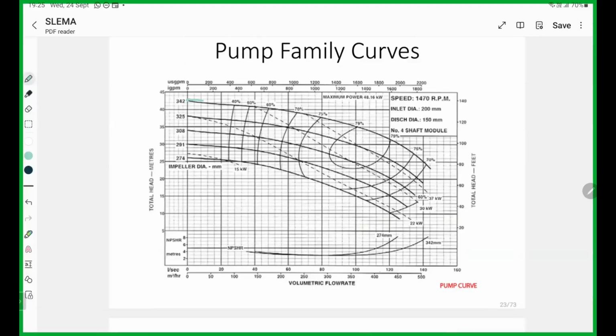This is higher impeller diameter. Then you can choose your impeller diameter and system curve. Then you can select your pump as per your requirement. You have to provide your head and flow basically to select the pump. Then accordingly, the pump manufacturer provides what your impeller diameter is, right? That is one thing you have to keep in mind. Then we have pump systems. They have family curves. That means the casing is the same, but pump performance may change. That's a very important one. Yeah, we just look at the pump.